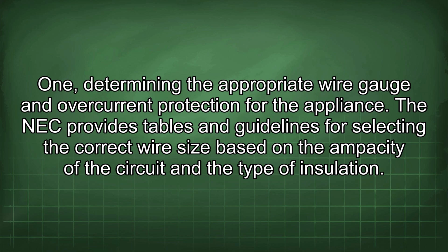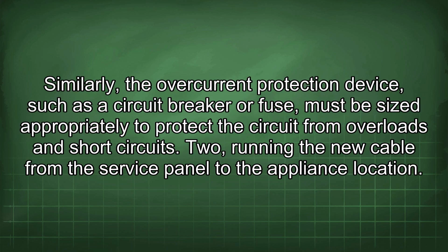1. Determining the appropriate wire gauge and overcurrent protection for the appliance. The NEC provides tables and guidelines for selecting the correct wire size based on the ampacity of the circuit and the type of insulation. Similarly, the overcurrent protection device, such as a circuit breaker or fuse, must be sized appropriately to protect the circuit from overloads and short circuits.